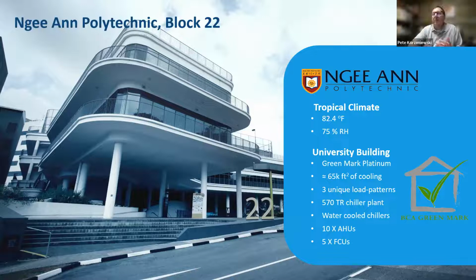So the building was having a really hard time trying to maintain temperatures in the spaces. They were getting a lot of complaints from the occupants, and they were not achieving the design delta T. They weren't achieving it from day one and weren't achieving it a couple of years later, when the frustration really built.